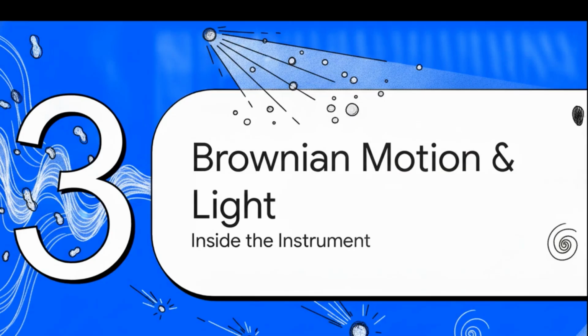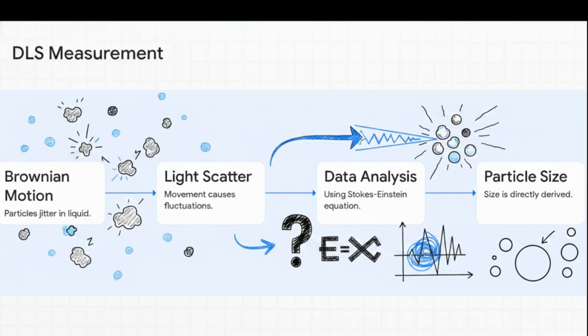Which leads us to Section 3, Brownian motion and light. Okay, so how does this actually play out inside the instrument? Let's break it down. Step 1. The particles in your liquid are undergoing Brownian motion. They're just randomly jittering around as they collide with solvent molecules. Step 2. You shine a laser on them, and this random movement causes these tiny fluctuations in the intensity of the scattered light. Step 3. The instrument captures all that fluctuating data and analyzes it. And finally, Step 4, boom, the particle size is derived from that analysis.